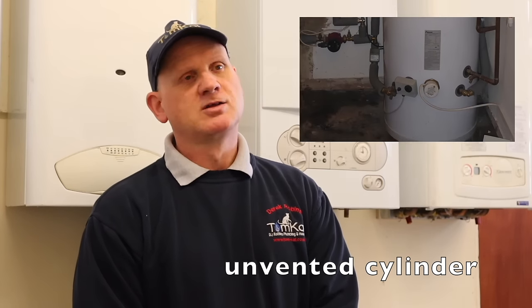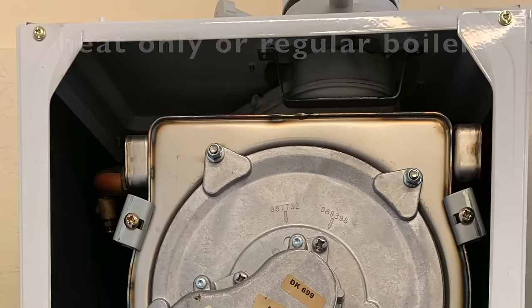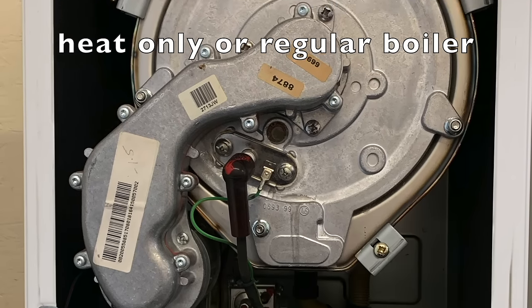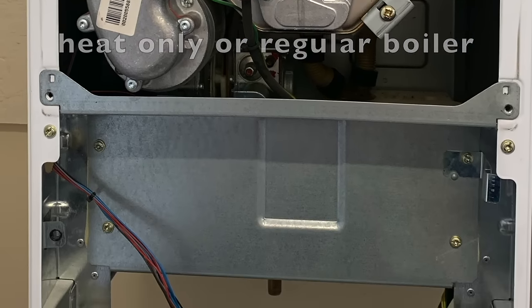And that's the same for a regular or heat only boiler, sometimes known as a conventional boiler, which has nothing in it, only really the burner and the heat exchanger, and all the external controls, the pump, expansion vessel and controls, cylinders, would need to be separate from the boiler. With the combi boiler though, it normally gives you a greater pressure at the taps than you would actually get from a heat only boiler with a vented cylinder. But that's not necessarily true if you've got an unvented cylinder, because unvented cylinders are also piped direct off the mains, so they would give you the same pressure as your cold.